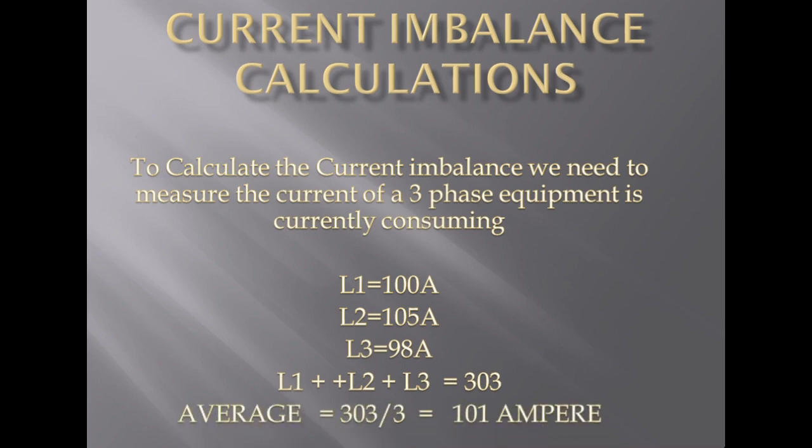In this tutorial, we will learn current and voltage imbalance calculations. To calculate the current imbalance, we need to measure the current a three-phase equipment is currently consuming. Let's assume L1 is 100 amperes, L2 is 105 amperes, and L3 is 98 amperes. By adding L1, L2, and L3 and dividing the sum, which is 303, by 3, we get the average measured current of 101 amperes.